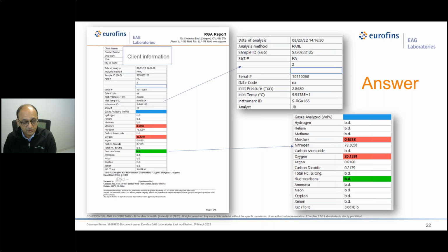So either I puncture and the gas goes to the sample chamber, that's the change. Before that, the sample chamber is sitting at the 10 to the power minus 8 torr range, and this 2.86 torr in this particular case shows that when I punctured the sample, this much gas was introduced into the mass spec.